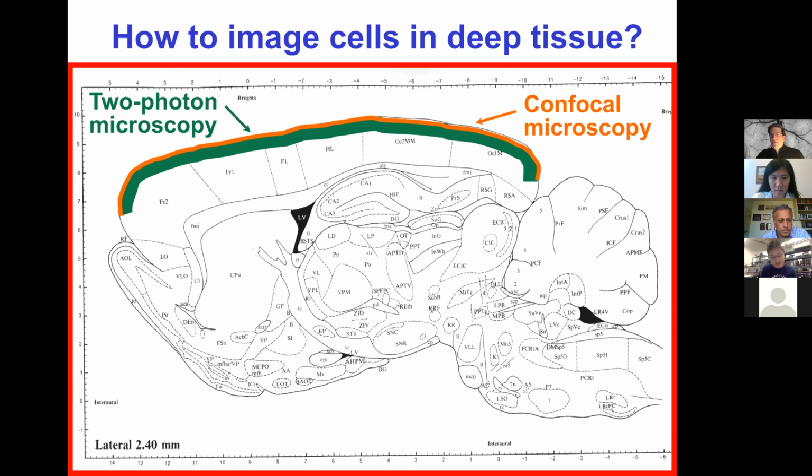The third question is, what could be the ideal laser parameters in terms of the central wavelength, specifically for those multiphoton imaging microscopes, and then pulse duration or peak power or something like that? Yeah, so the most common laser that people use is typically the Ti-sapphire laser, because there are multiple attractive parameters. First of all, people like the tunability, so you can excite different dyes or fluorophores with different absorption spectra.